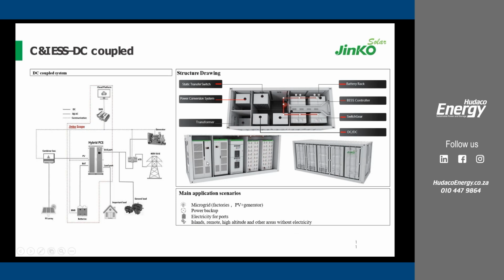You'll find that, like I did mention, we have the PCS, and we also have the DC-DC converters. The function of the DC-DC converters is basically more of the MPPTs. Each DC-DC is usually rated at 50 kilowatts, so each 50 kilowatts is basically an MPPT, and it usually has one input connection, a positive and a negative. The voltage range for the DC-DC is usually between 250 and 850 volts.